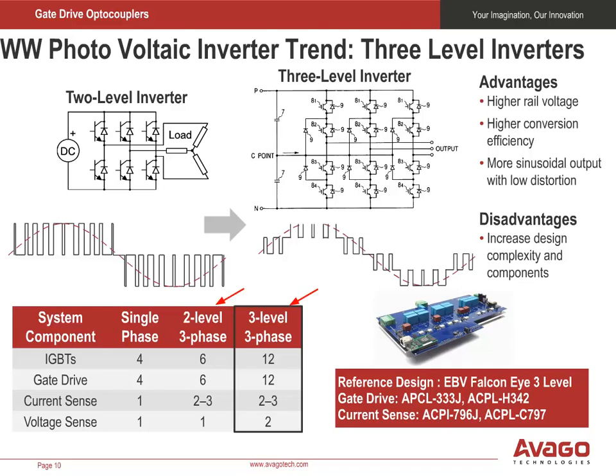This slide compares a dual-level inverter to a three-level, three-phase inverter. The total number of gate drivers, plus current and voltage sensors needed, are shown here. The advantages and disadvantages of a multi-level, three-phase inverter are also shown. Although more complex to design, the three-level, three-phase inverter has a higher rail voltage, higher conversion efficiency, and a more sinusoidal output that results in lower distortion.